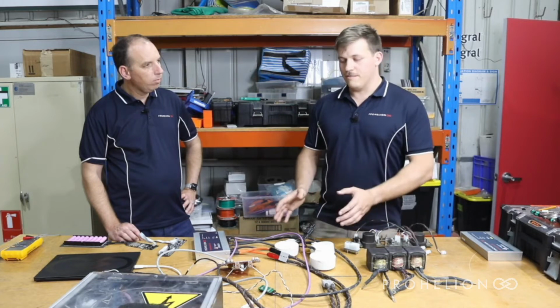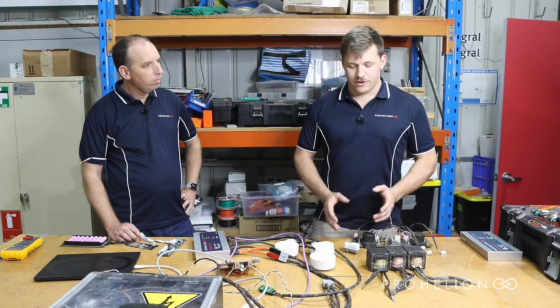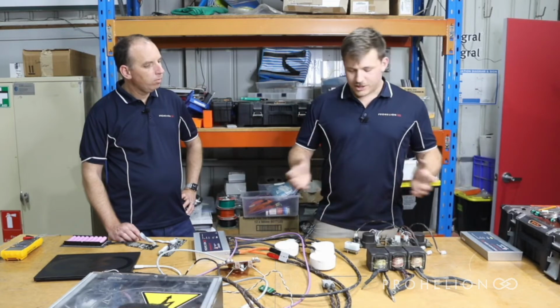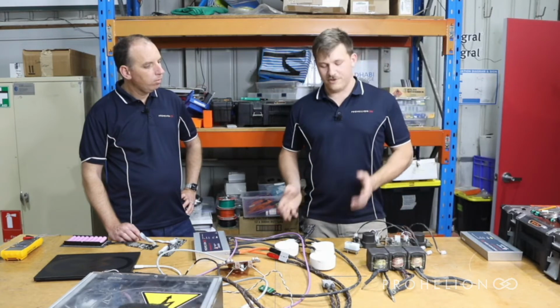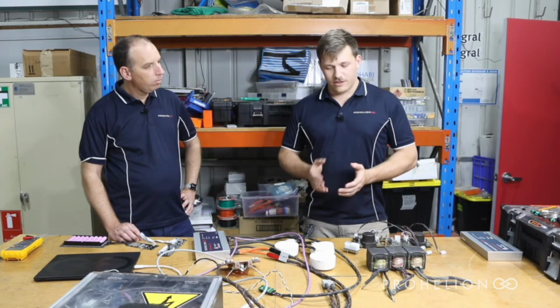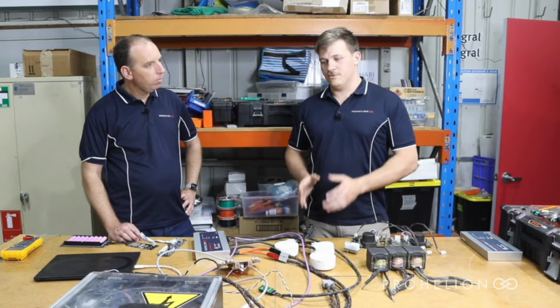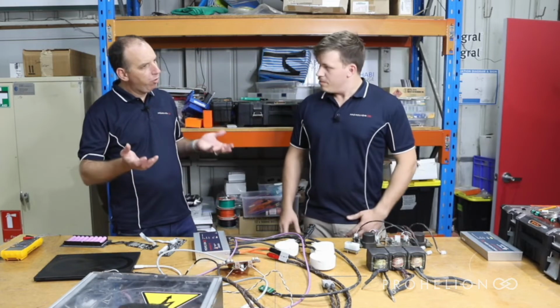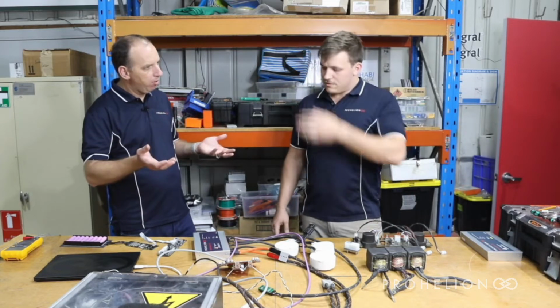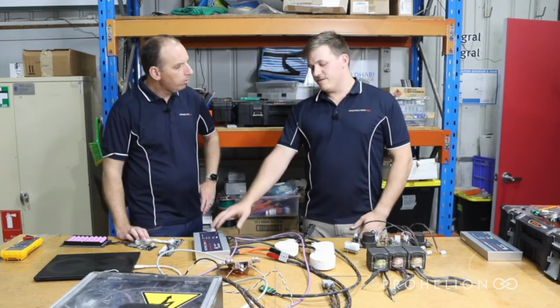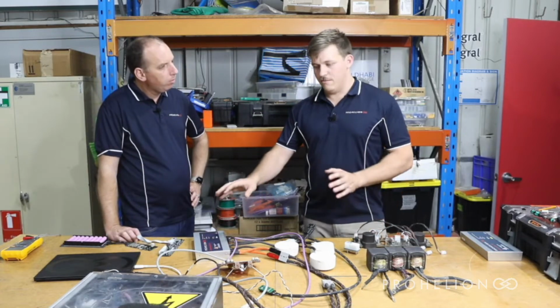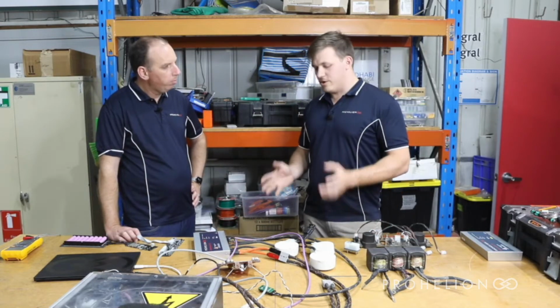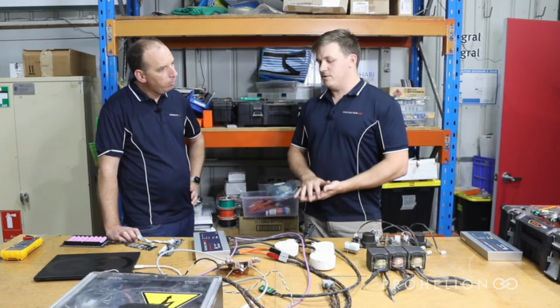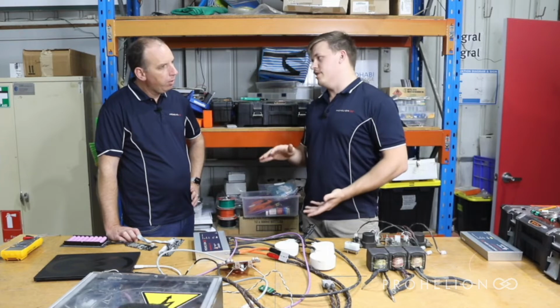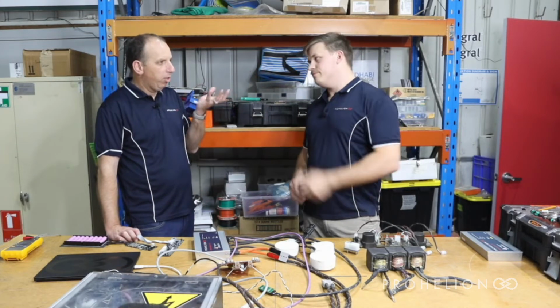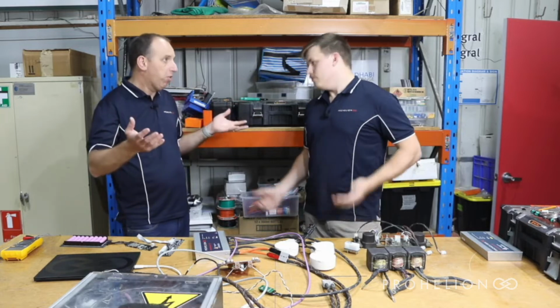So when you're connecting a battery to a wider system, it's really important that you do something called precharging. Precharging sounds complicated, but it's pretty simple. All you're trying to do is lower the inrush current to an acceptable level for your system. So we're basically trying to balance the voltages effectively up. Is that what's happening here? Yeah. So you can consider any capacitance on the wider system being at 0 volts when you go to turn the battery on. And you're trying to bring that voltage up to the same voltage as the battery in a controlled manner. Yeah, so nice and slow, bring it up, and then we've got the ability to engage the pack at that point because things are more balanced on each side.